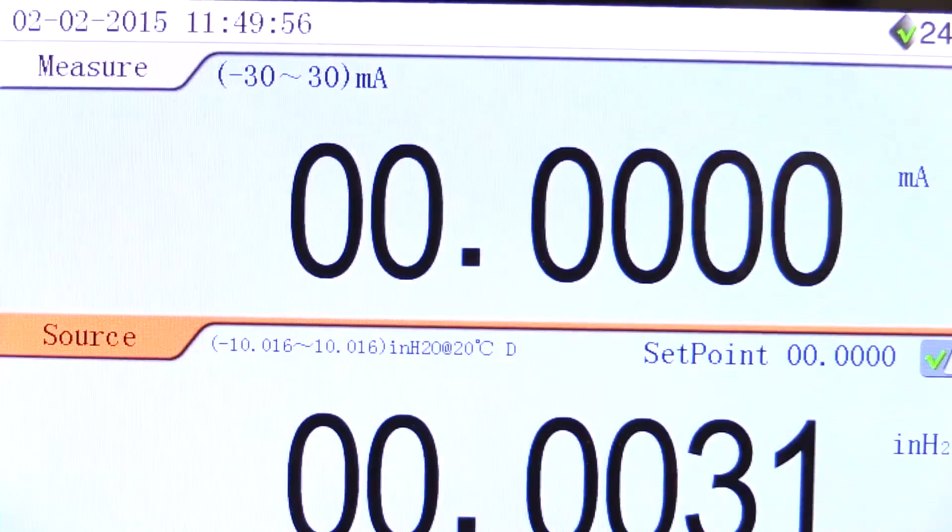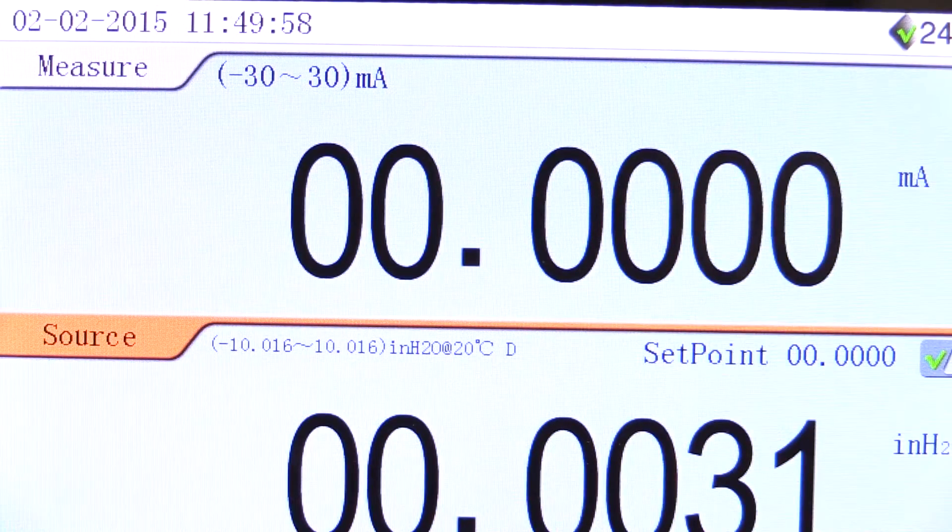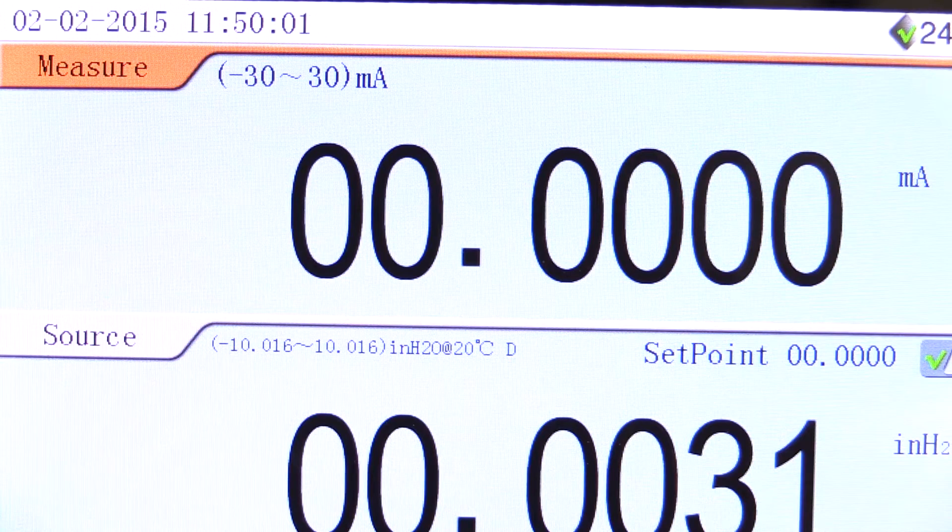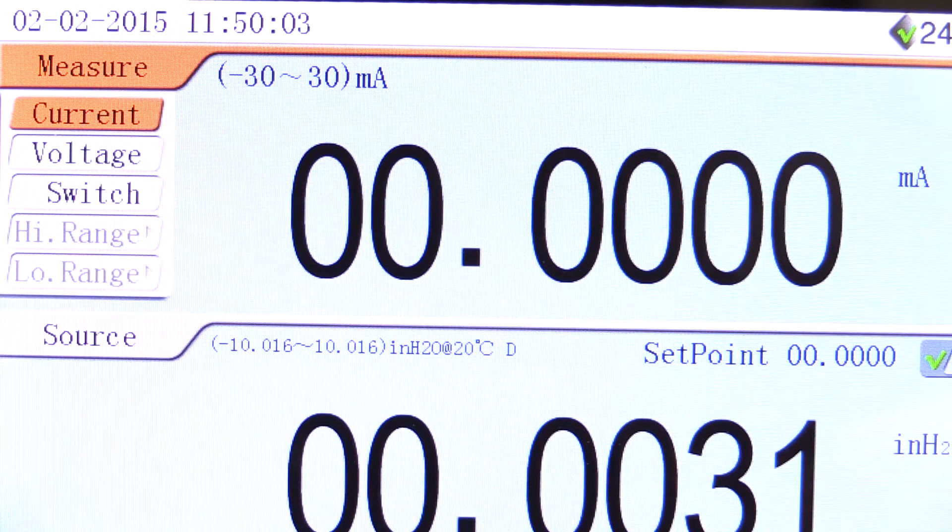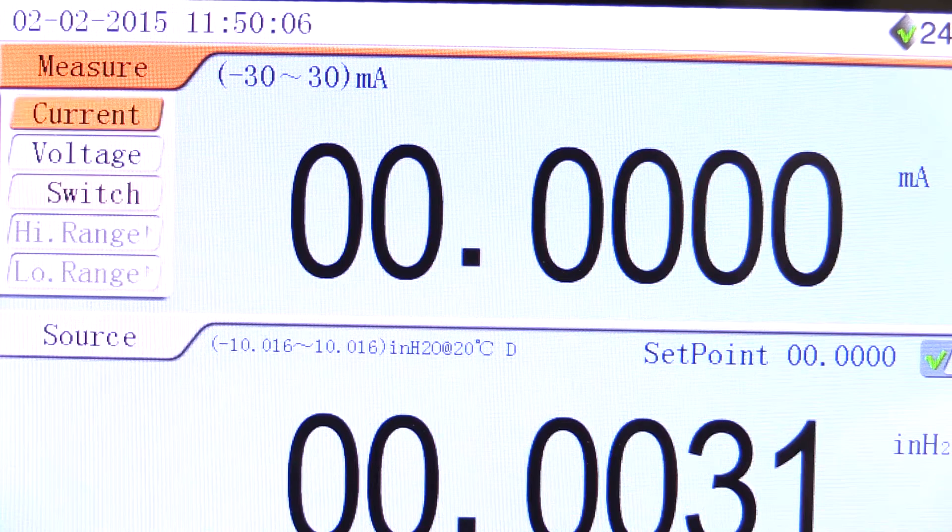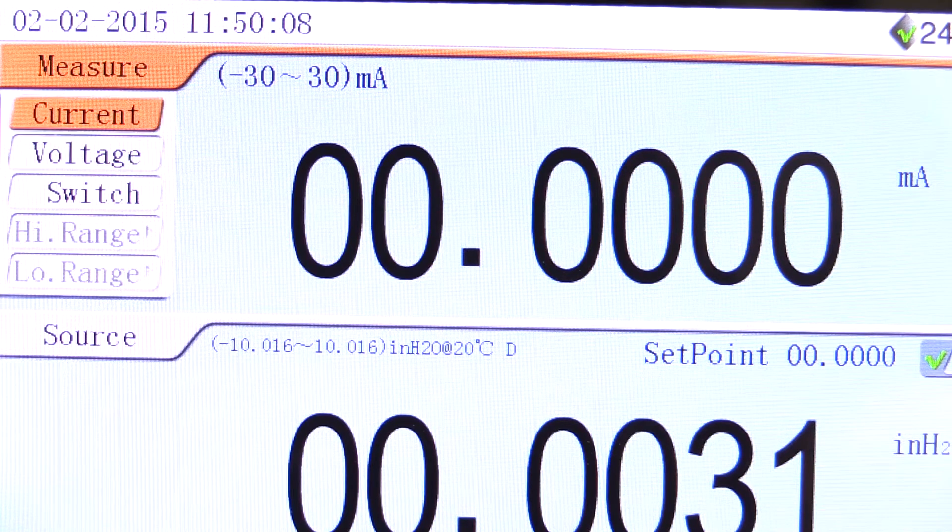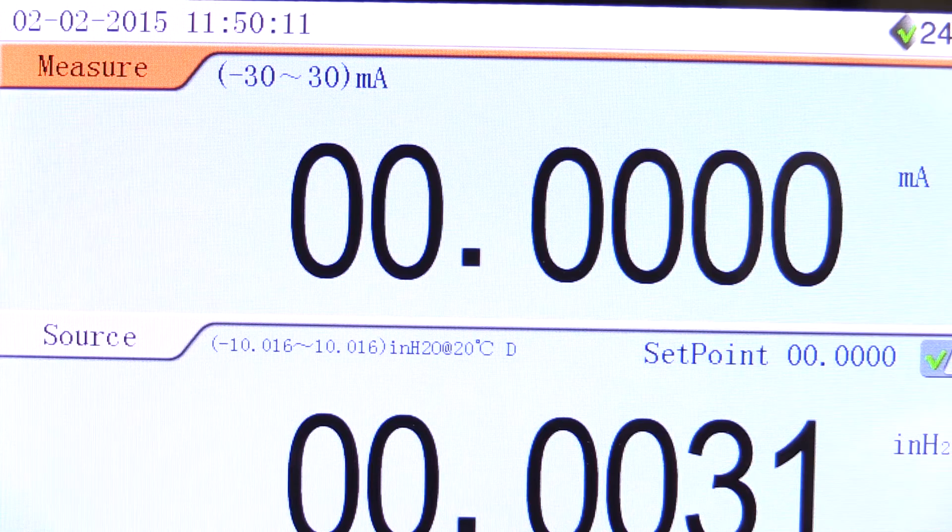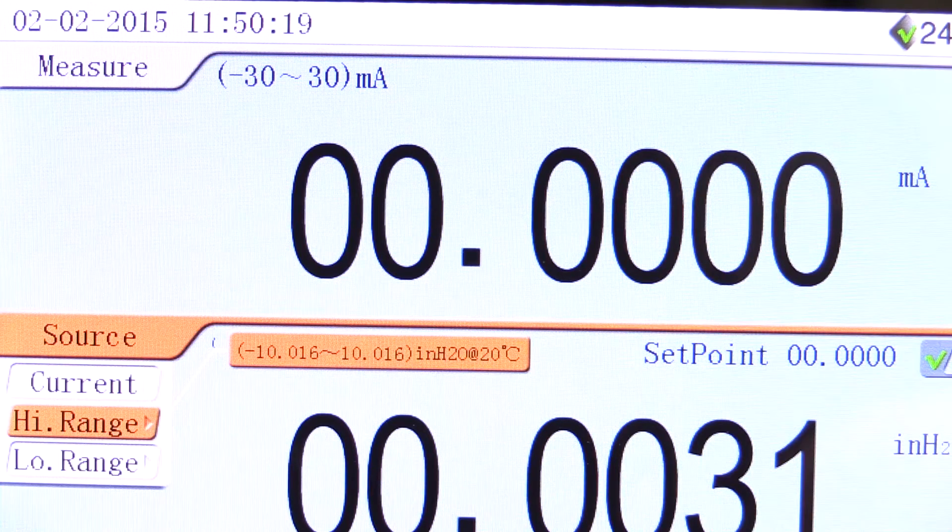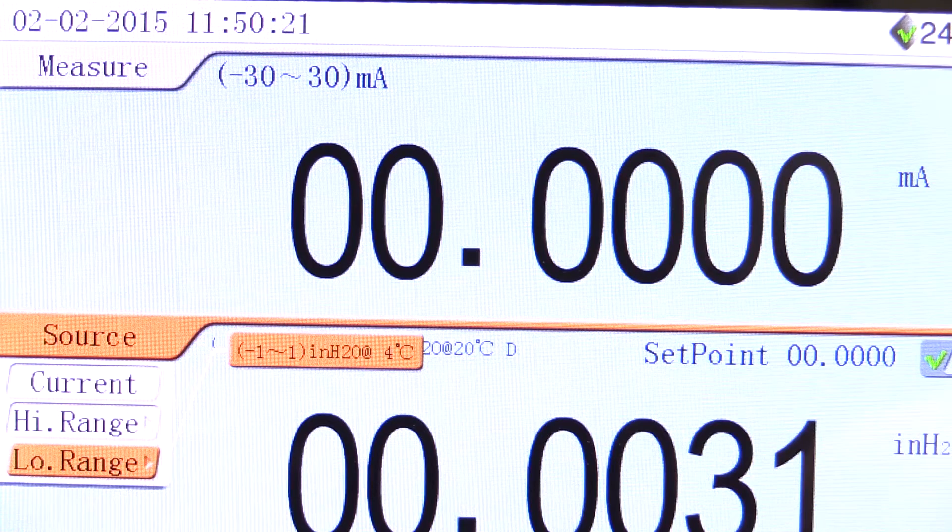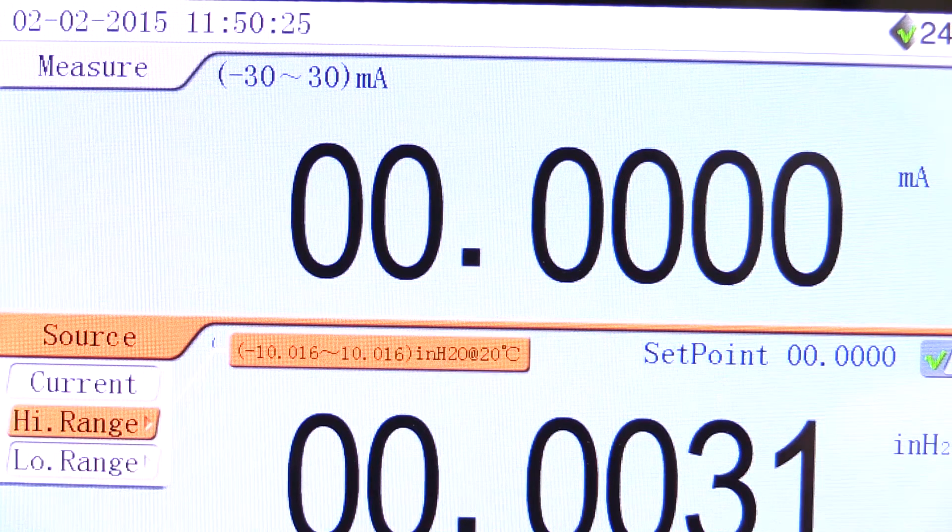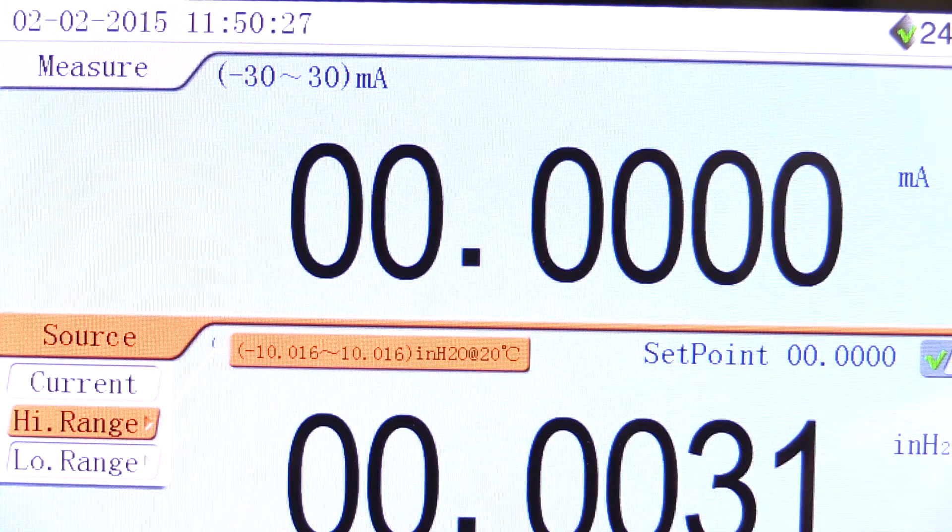The ADT-761 has a split screen that shows measure and source windows. In the measure window, by selecting measure, the appropriate setting is selected to read the transmitter. In this case, current is the selection we need. In the source window, select source and ensure the appropriate sensor range is selected for the device under test. In this case, plus or minus 10 inches of water is the best selection for this transmitter.